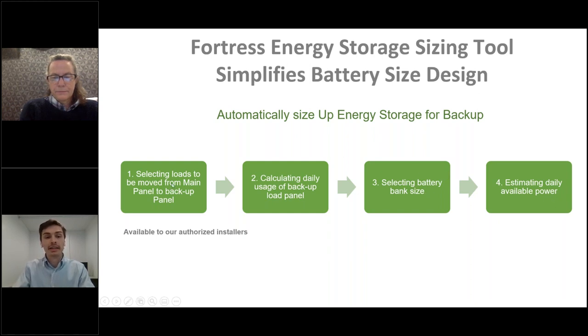Sizing is critical, and taking these four steps is very important. Let's say you're using an emergency power application and you undersize the battery. Then you're over-promising and under-delivering on what your battery is going to provide to the electrical loads in your customer's home. And if you oversize the battery, there might be problems with too long of charging times.